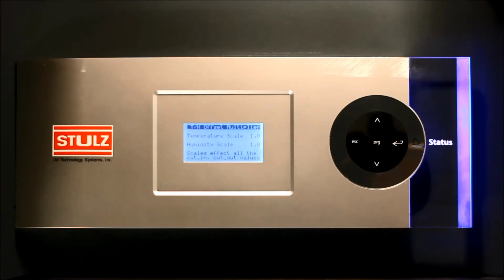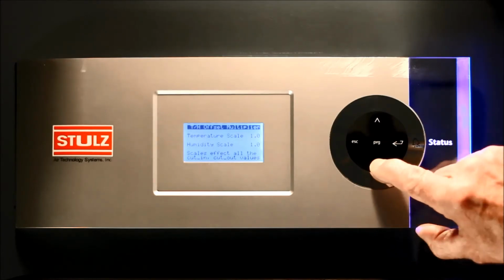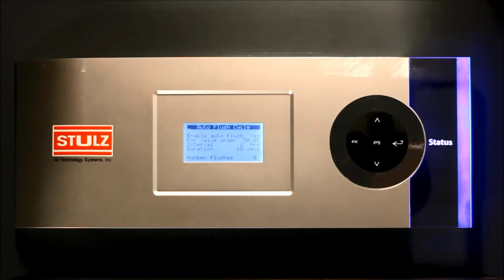Continuing on, we come to the auto flush cycle feature, and here we may enable a periodic flushing of the chill water, free cooling, or alternate water source coils. To enable this feature, change the word no to yes, set the desired minimum valve open percentage, and set an interval time so that if the valve does not reach the minimum open position in the allotted time frame, a flush cycle will occur. At the bottom of the screen, you will find the displayed number of how many flush cycles have been completed since the unit was initialized.